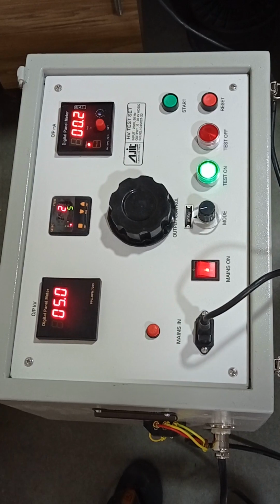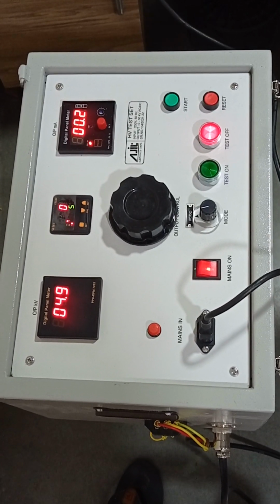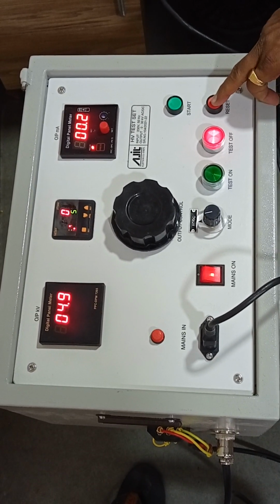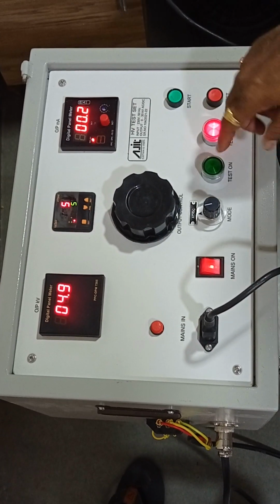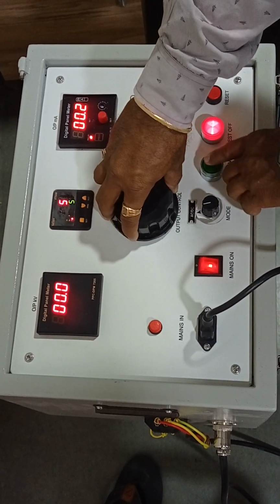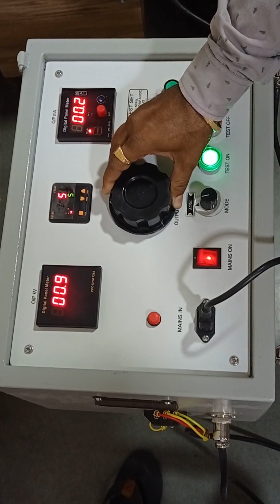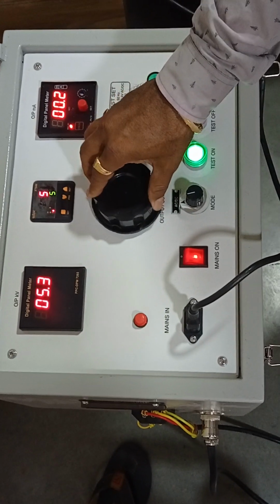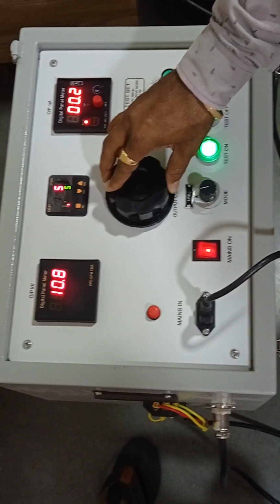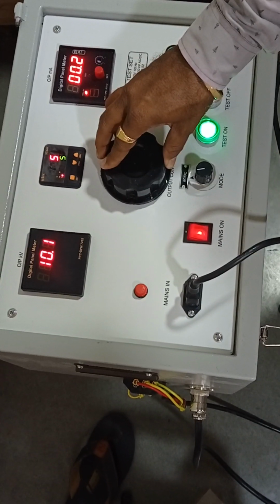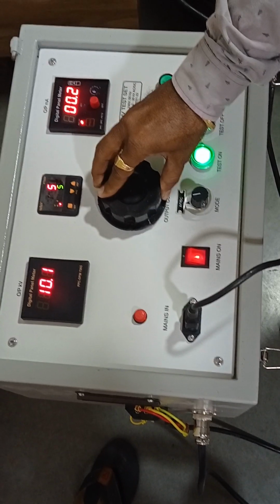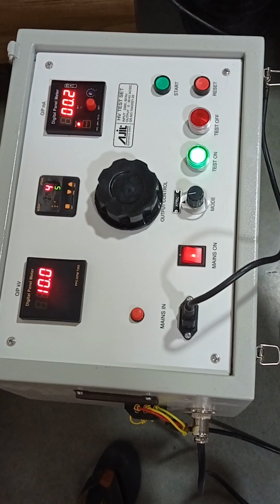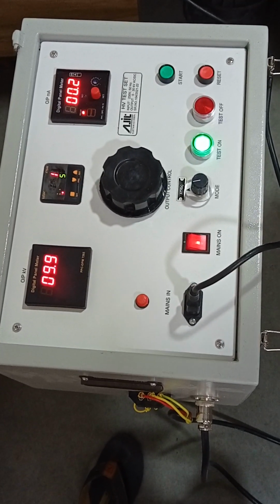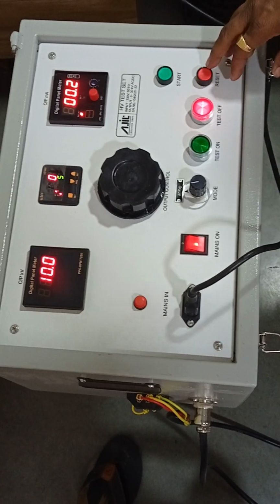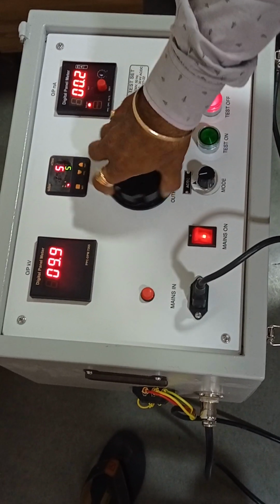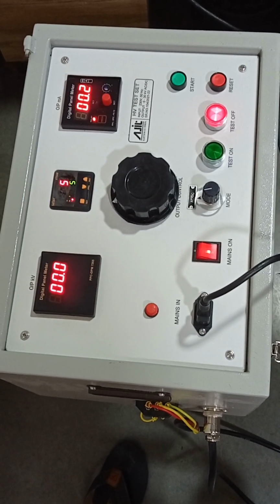The timer will start counting down. Once the time is over, it will trip off the output of the instrument. Now again we can reset it. Again we have to come to 0 and start. This way we can use the high voltage tester. Now if we want to test at 10 kV, set the output at 10 kV and then start the timer. The 10 kV test will be conducted for 5 seconds and after that it will trip. So this is the way. Now we can reset it for the next test. This way we can test or use the high voltage tester in AC mode.